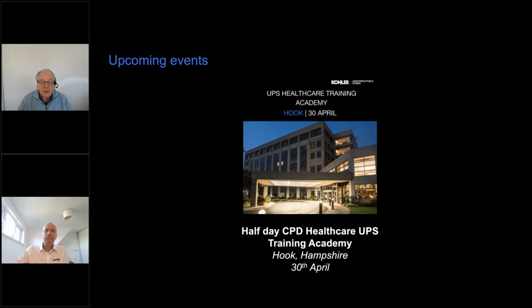Yeah. Couple more questions. Can I use a PV array to charge the UPS batteries instead of mains? In theory, yes. But the best way of doing it is to keep things separate. The UPS is there in case you need it. It's a critical supply. So if you've got PV on your property, it's always best to have that just feeding into the input supply onto your input board of your facility. Therefore you are reducing the consumption from your mains, and if the battery is recharging, it will use the power coming from the PV rather than the mains. But then the UPS is always there as a critical backup if you need it.